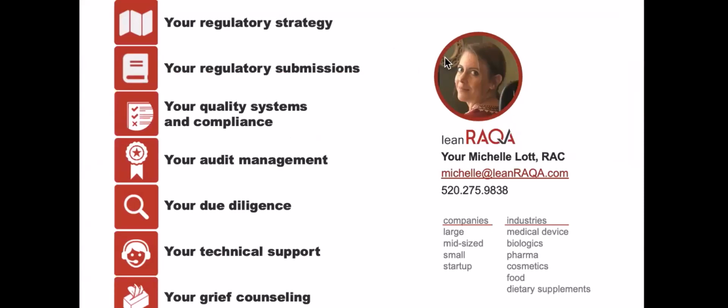With that, I see we had a question come in. Juan says, is there a counterpart to GSPR and performance regulations for the US? Or are those requirements for medical devices only determined in the QSR? So right now, there is no counterpart to the GSPR in the United States.